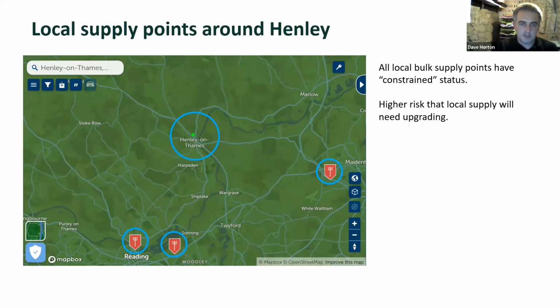Just to go off on a bit of a tangent - when it comes to actually installing these fast charge systems, you really have to be conscious of the local grid supply. In some respects the system is friendly to the local supply, because you're only looking for a low power, low voltage, really a 3-phase connection, no different to what you might have in your house, rather than something that comes off the 33,000 volts or higher part of the network. To charge those trackside batteries, we've assumed you just need a 415 volt 3-phase 65 amp connection.